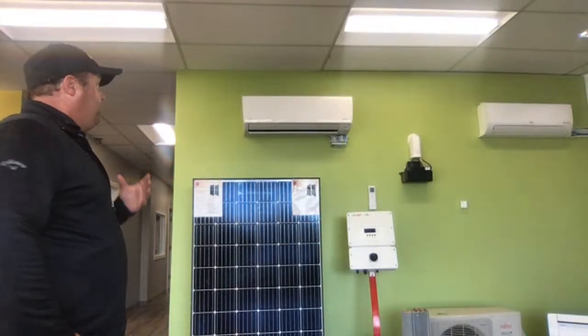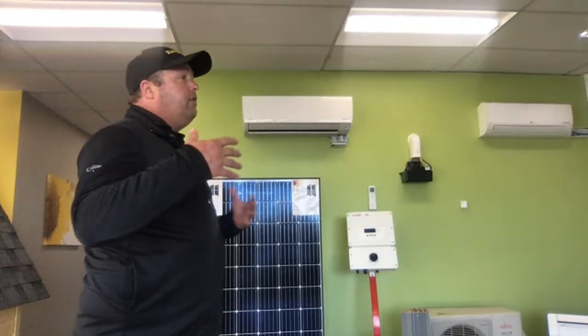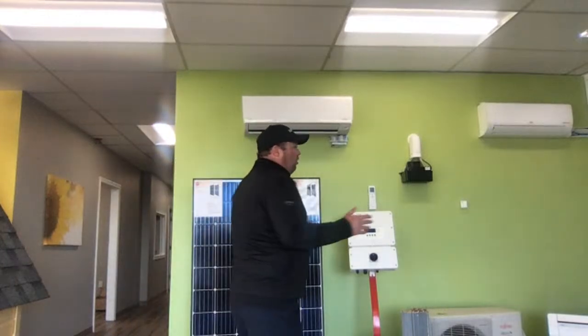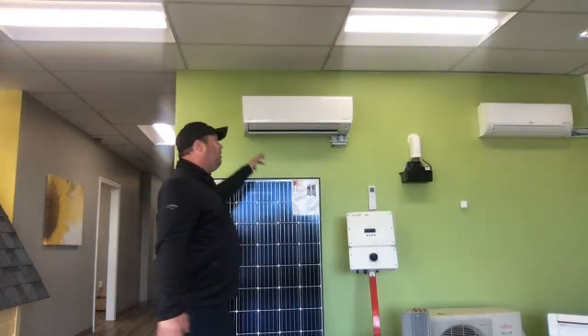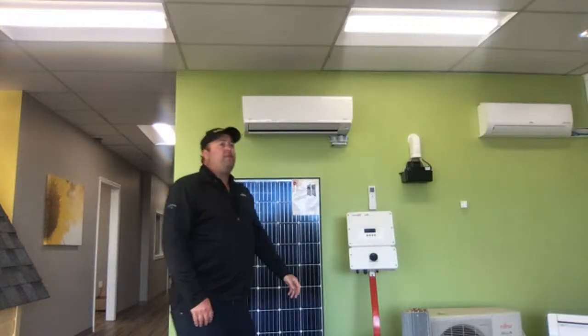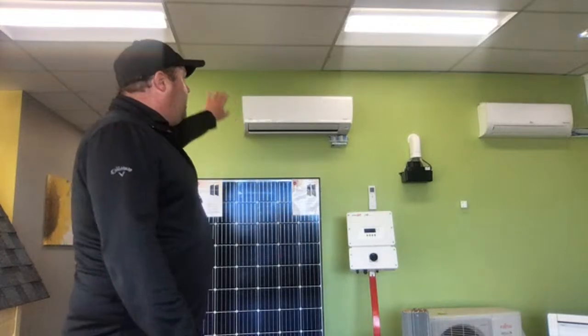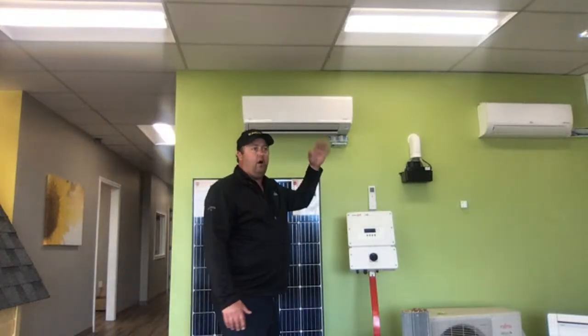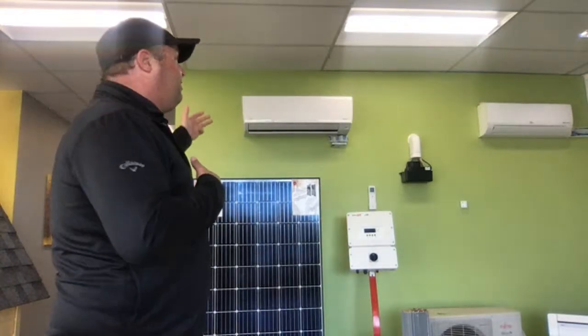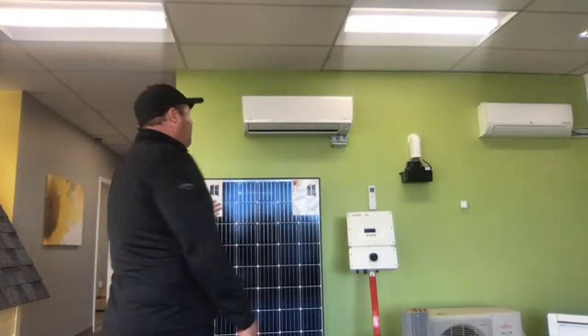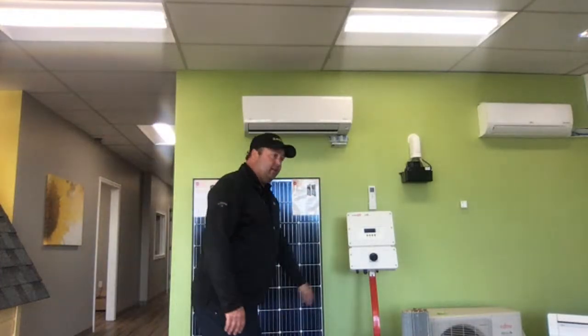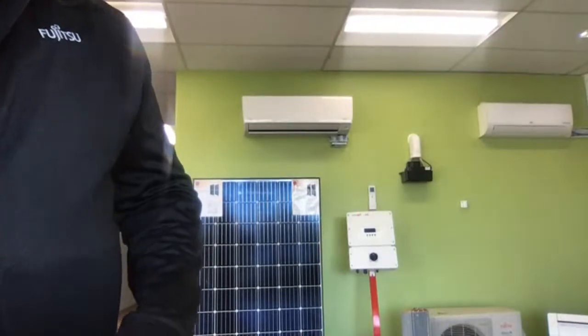Me personally, I've been doing this a long time, probably been in 30,000 houses over the last few years. I kind of compare it to about a 70-cent liter of oil. So if home heating oil is 70 cents a liter, you're going to break even with the heat pump. If oil is a dollar a liter, you're going to save somewhere around 30 cents on the dollar by using the heat pump. If oil goes up to $1.30, you're saving 60 cents. But right now it's at 50, so in the wintertime this would actually lose you 20 cents on the dollar because oil is so cheap. But it's not going to stay cheap that long, and we all know that's going to go up.